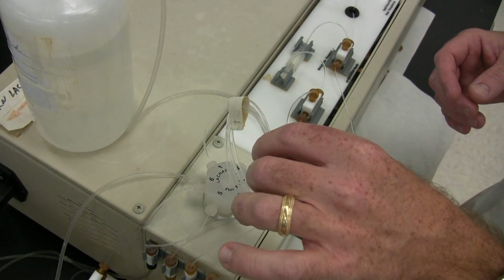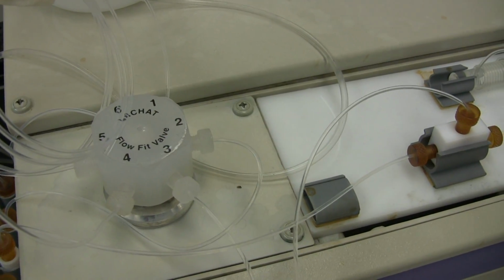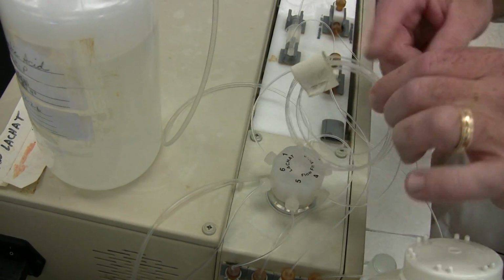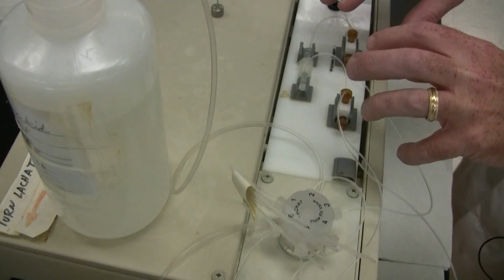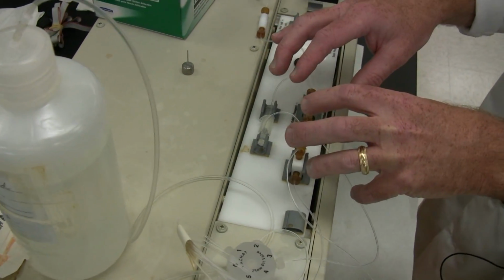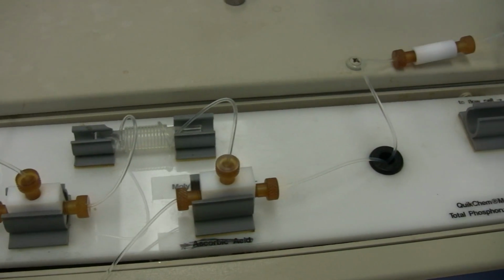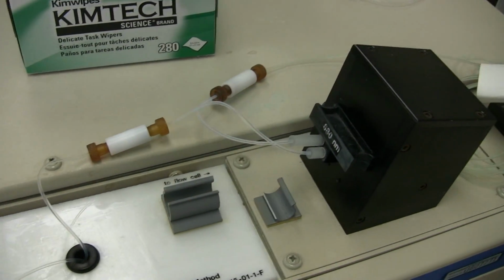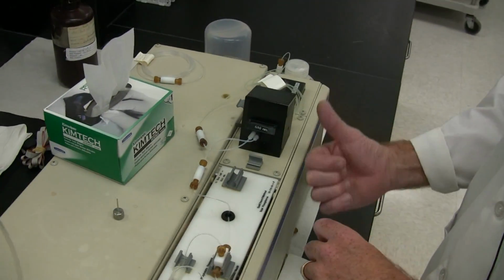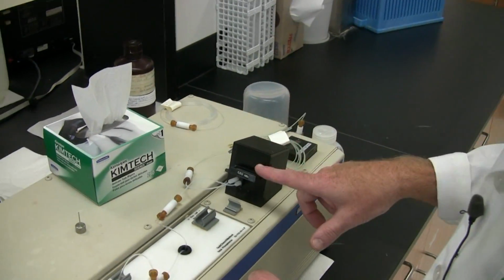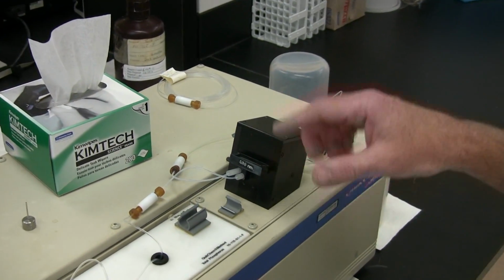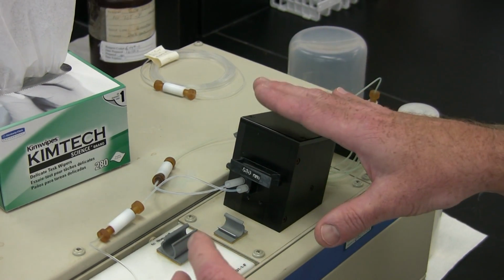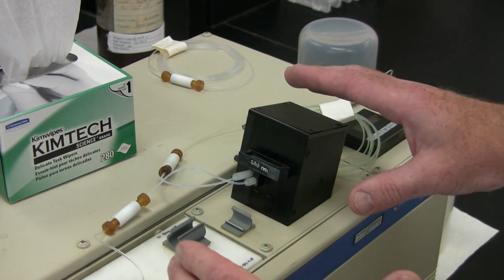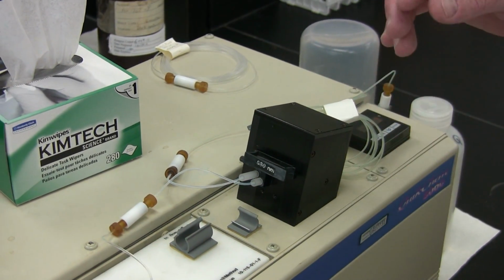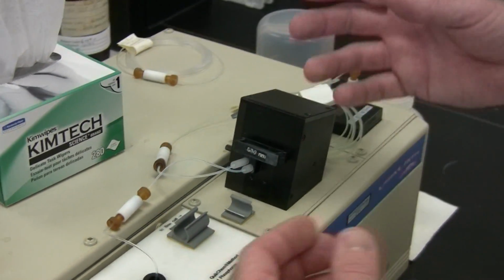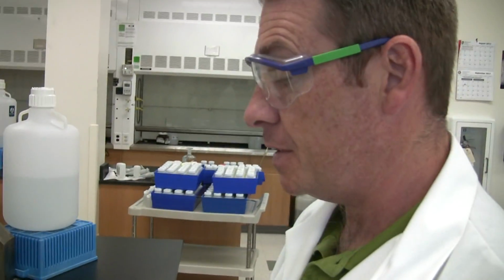The sample comes into this valve and loads this sample loop, then the valve toggles and injects this amount of sample. That reaction happens here, and a blue color develops. It's proportional to the amount of phosphorus. It goes through a flow cell. There's a light source shining a light, very similar to a spectrophotometer. We have a filter here at 880 nanometers and a detector on the other side. So that's how our absorbance is read. That absorbance is proportional to the blue color. So the higher the absorbance, the more blue color, and from a standard curve we can figure out the concentration of phosphorus in an unknown.